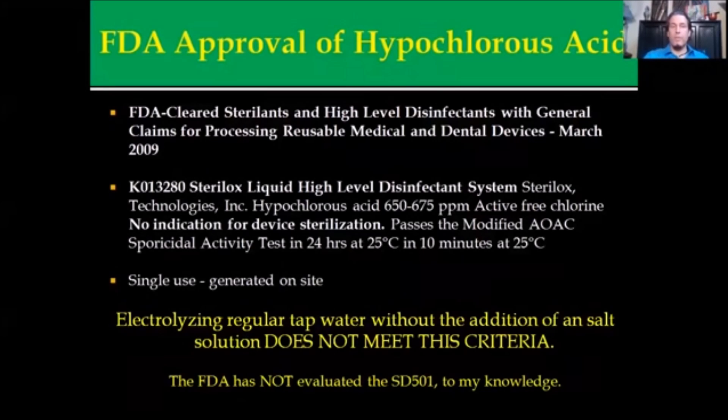It started off in 2009 with the FDA approval of electrolyzed hypochlorous acid, where it was cleared as a sterilant for reusable and durable medical and dental devices. The machine tested was a Sterilox unit with hypochlorous acid at 650 to 675 parts per million, and it was a 24-hour test where most results were rendered within 10 minutes. It's a single-use machine that generates hypochlorous acid on site. You can't store it and use it a week later — it converts back to its original salt water solution.